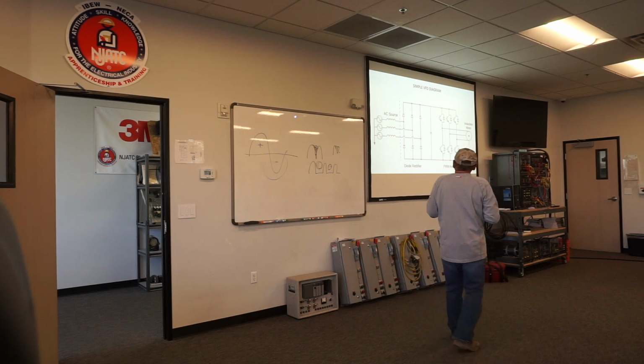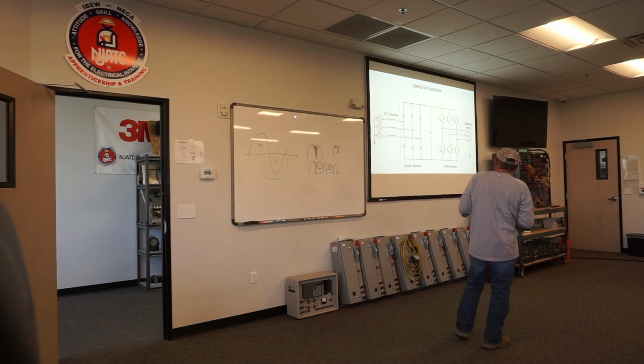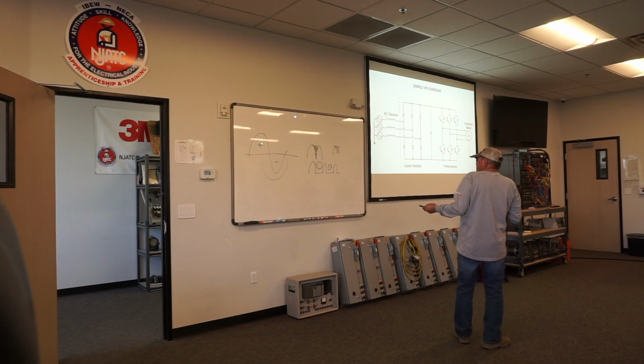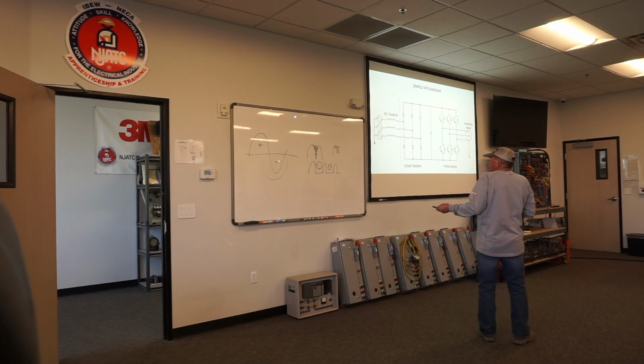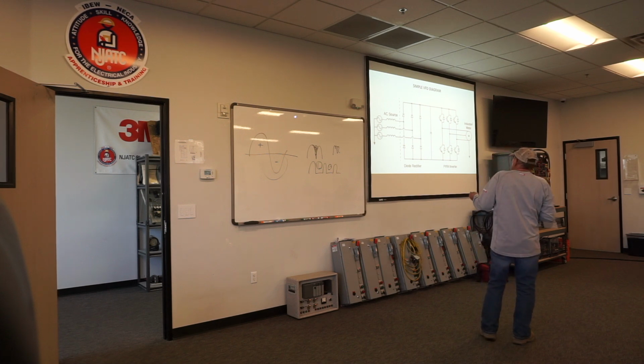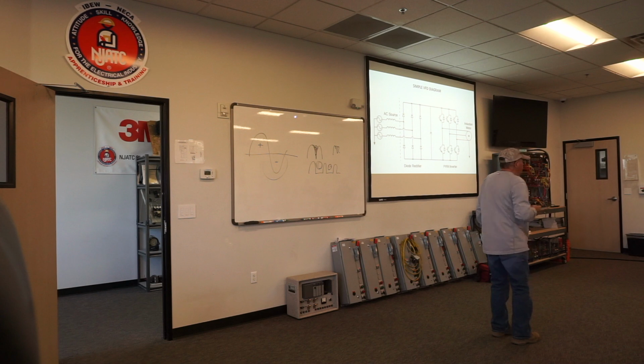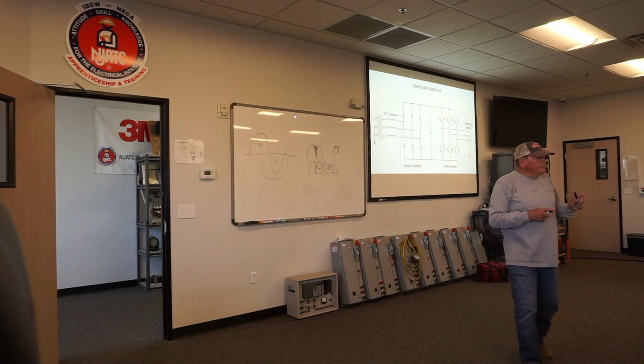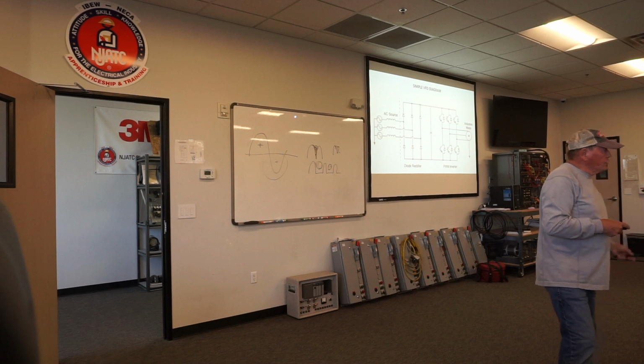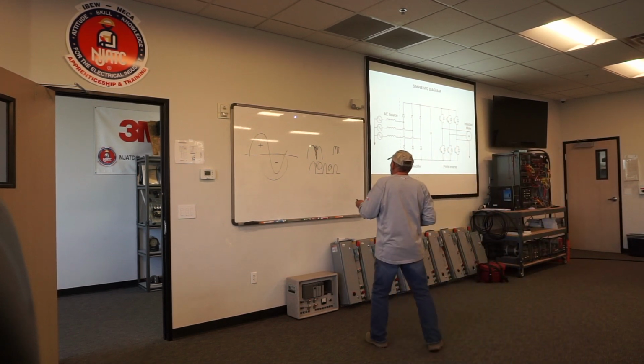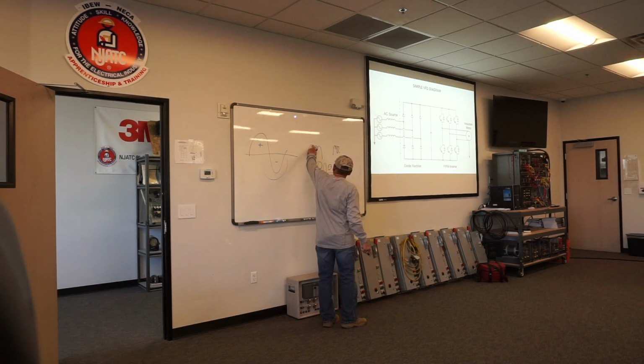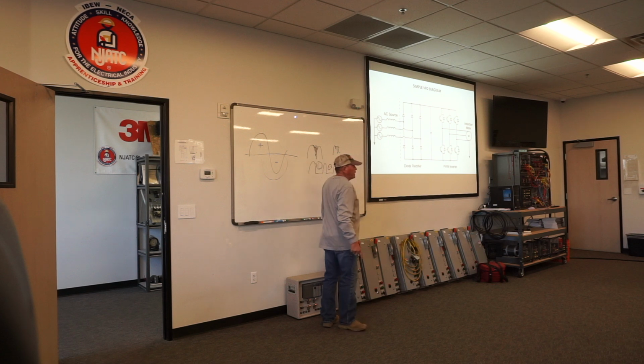So that's the purpose of this bridge rectifier. Two per phase, so I rectify this negative section, and I put out a DC signal on this DC bus, and there's the capacitor to fill in all that empty spot. So the capacitor charges as the voltage builds to here. My voltage builds up, fills up the capacitor. As my voltage drops off, the capacitor discharges and fills in the gap.